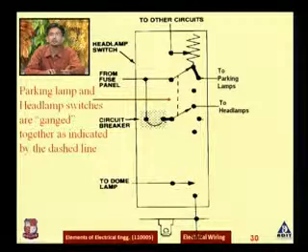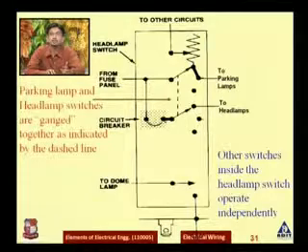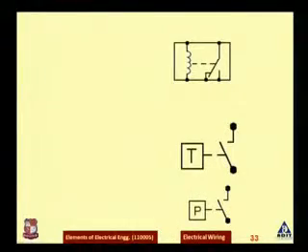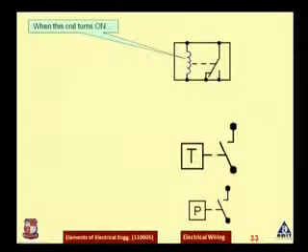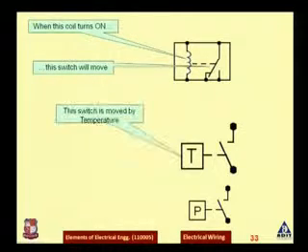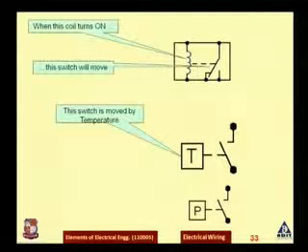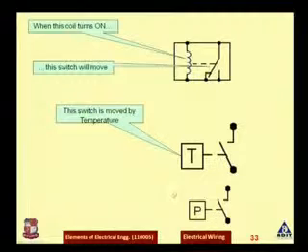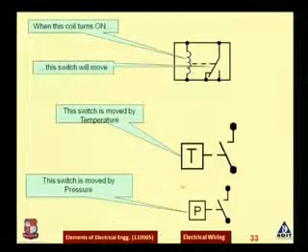The headlamps are also connected, and the switch inside the headlamp will operate independently. Some switches use a dash line to indicate when a coil turns on, the switch moves. A 'T' in a wiring diagram means the switch is moved by temperature. A capital 'P' with a dash line means the switch will be operated by pressure. These dash lines are used to represent different types of actuators in the electrical wiring diagram.